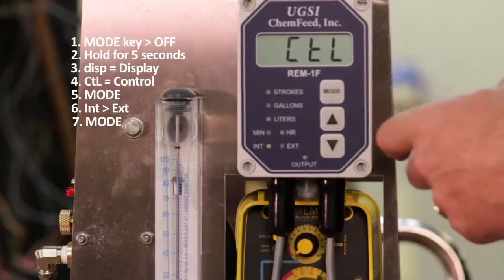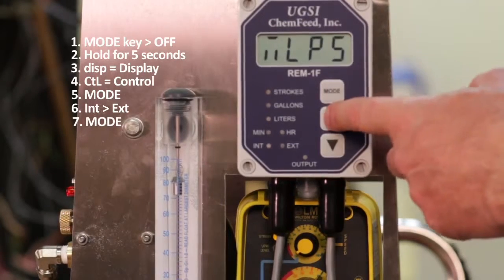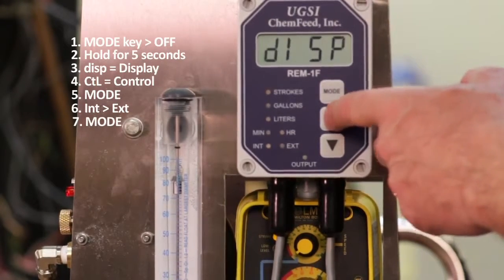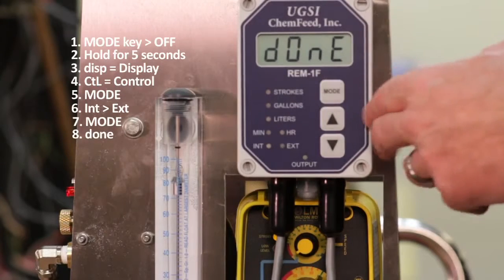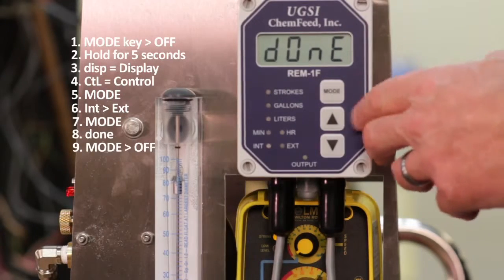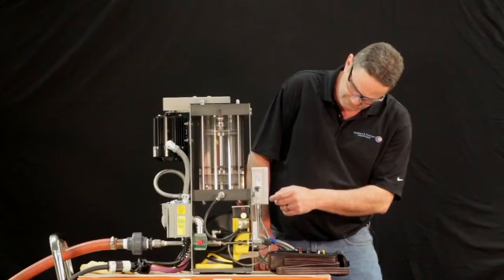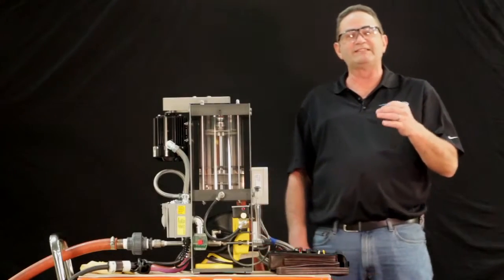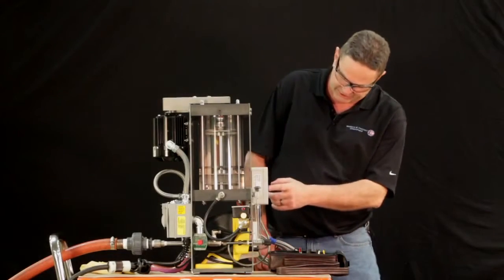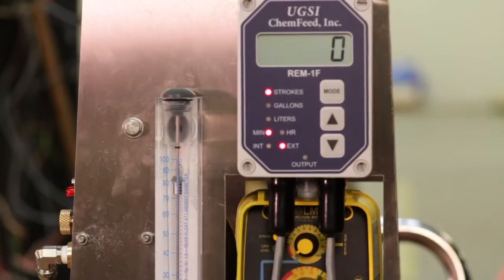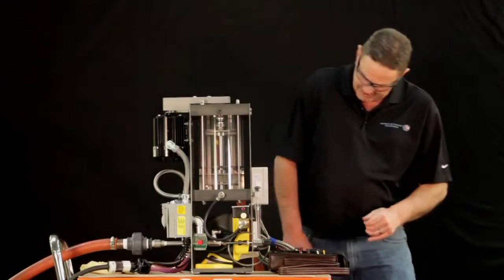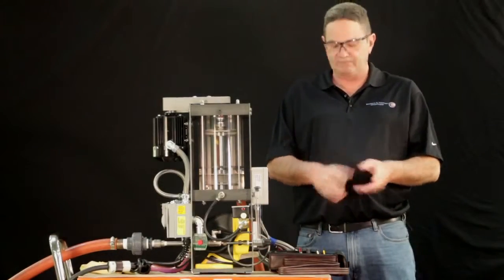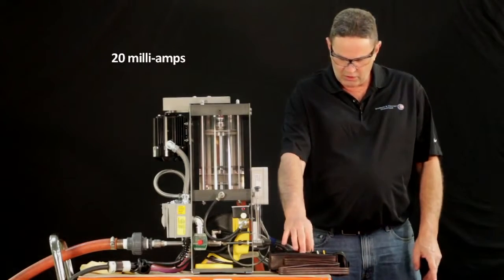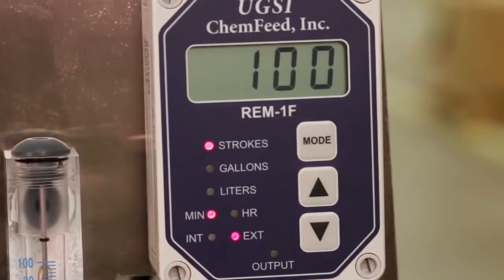Simply mode key, scroll up until you get the done prompt. At the done prompt, hit the mode. The unit is now looking for a 4 to 20 external source. Turn your pump back on by the mode key. You're now being controlled by an external source. 20 milliamps, 100 strokes per minute.